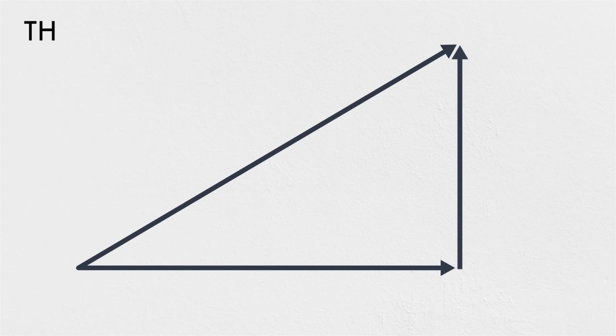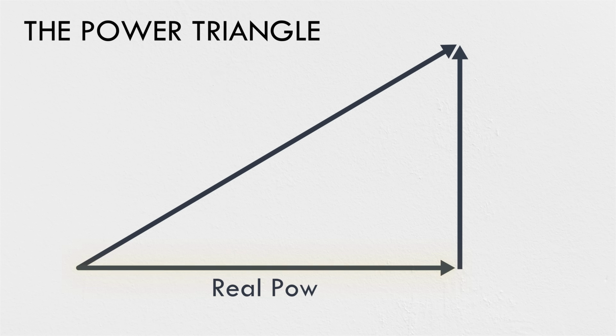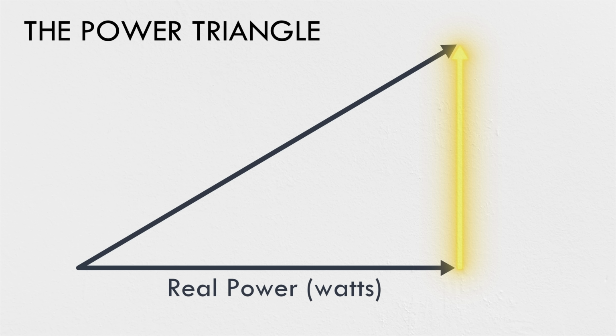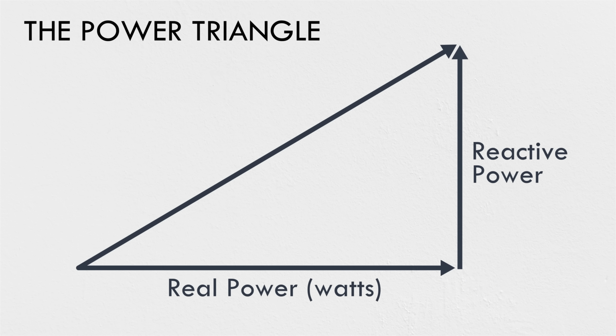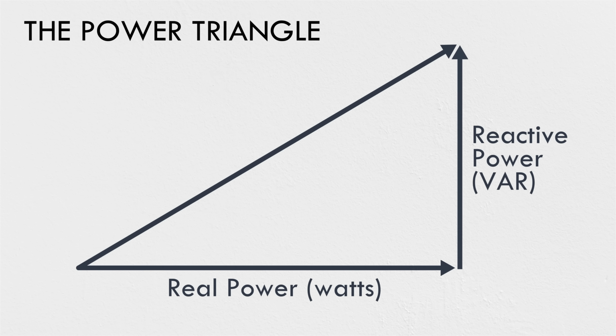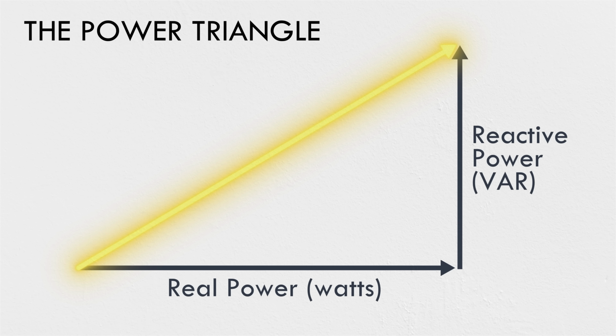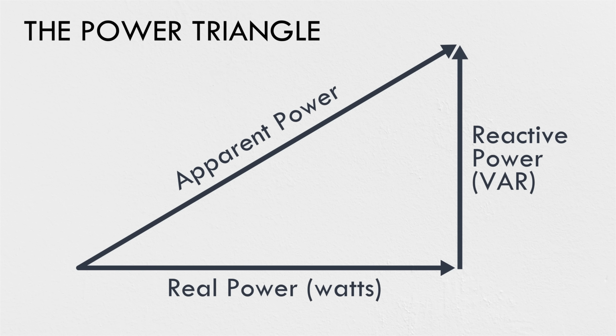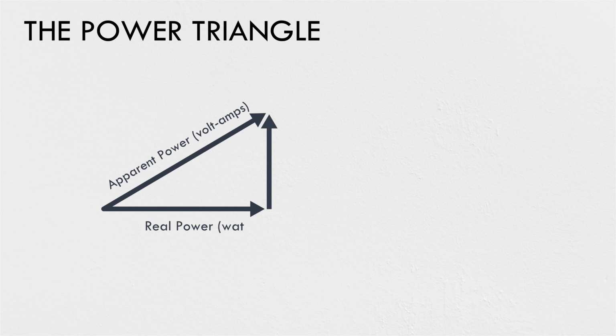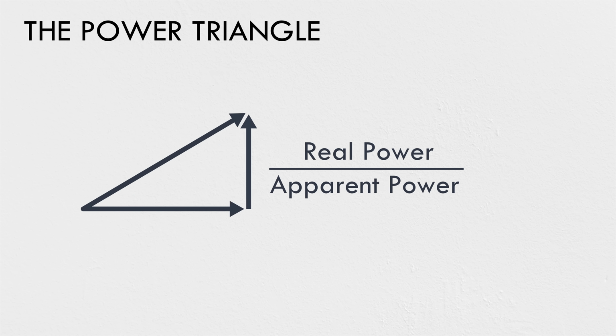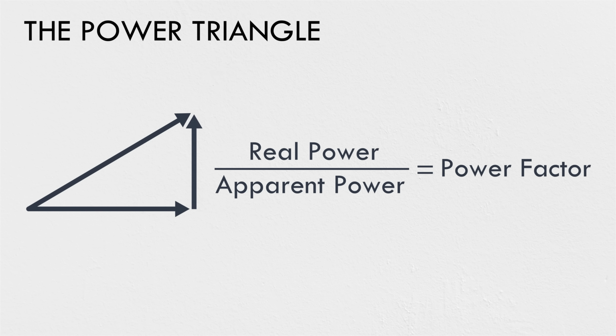But out of that math comes this visualization: the power triangle. This leg is the real power that actually gets consumed, measured in watts or kilowatts that you're probably used to. This leg is the reactive power that's returned instead of used, measured in volt-amps reactive, or VAR. By convention, we usually say that inductive devices consume reactive power and capacitive devices supply it. The hypotenuse of the triangle is the apparent power, the total amount of power that flows through the grid, measured in volt-amps. If you divide the real power by the apparent power, you get this ratio, called the power factor, a number that will be important in a minute.